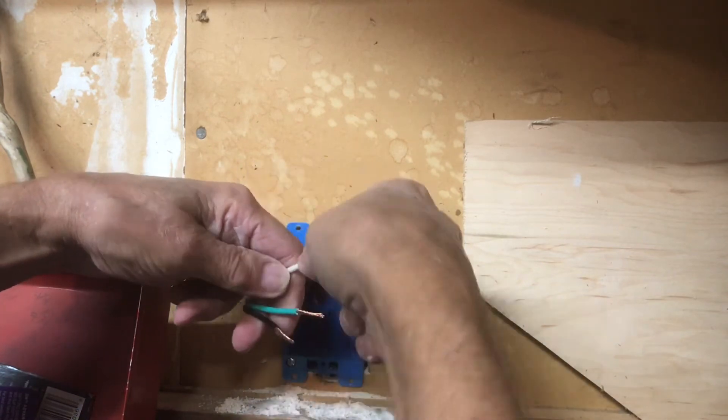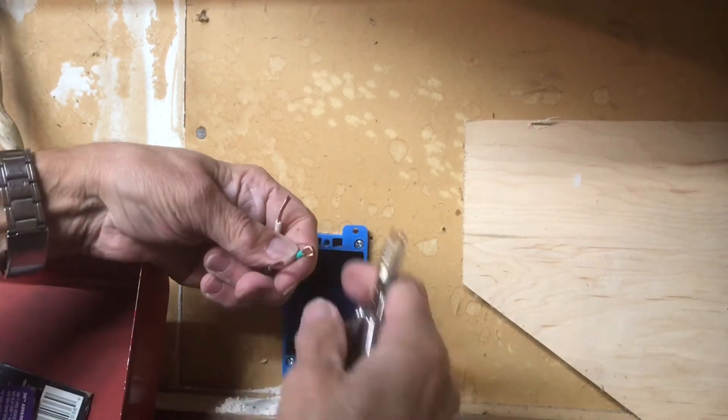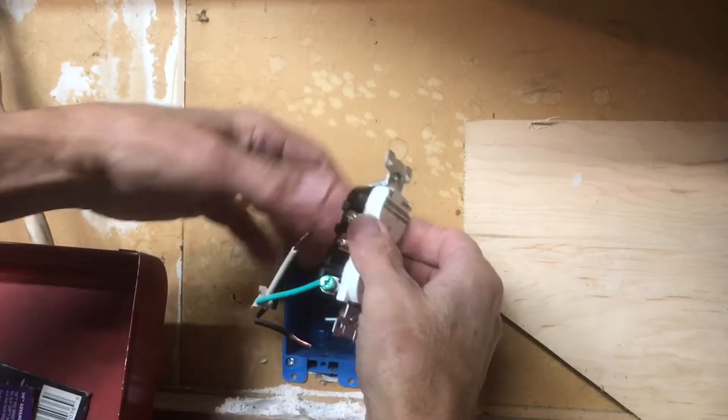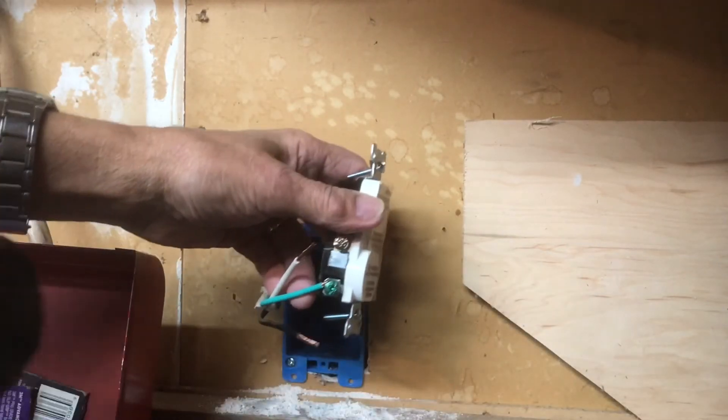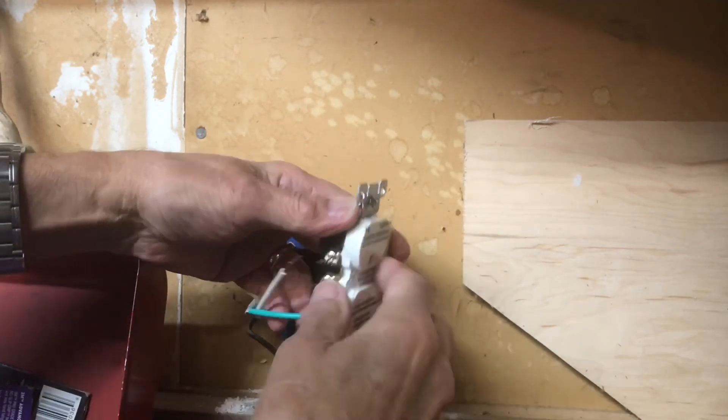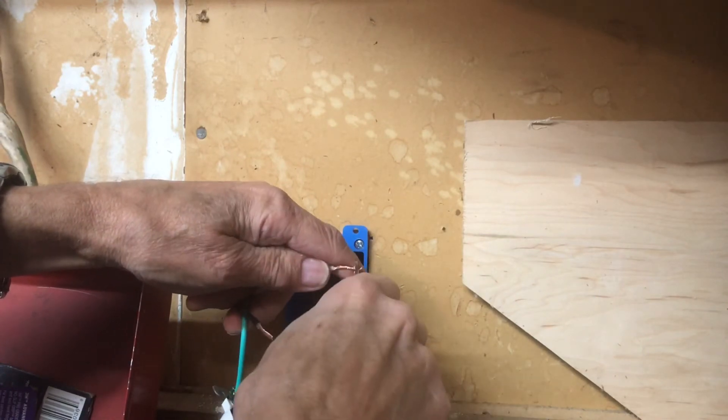So we're twisting these in the direction that they're wound, so it's clockwise. Then I'll take my little electrician's tool and I'll curl it around there so it goes on the ground wire in the direction the screw goes. That way it pulls the wire in instead of pulling it out.